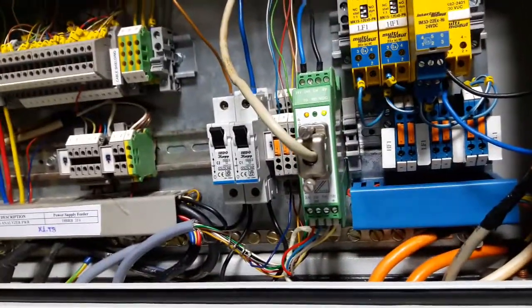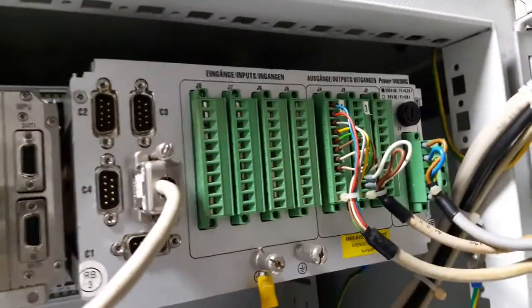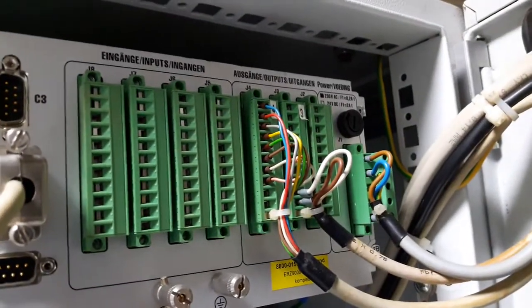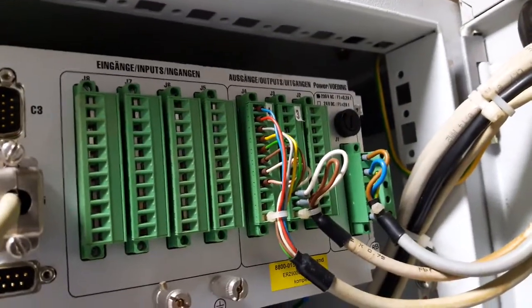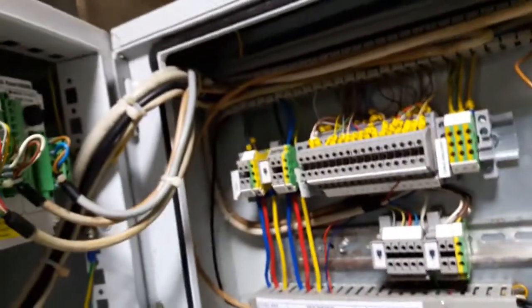You can see at the back of this display, this is the RS485, make Phoenix Contact. The top two are the 24 volts and the bottom are the signals coming from the sensor. And this is the back of the gas chromatograph. This is RS485, and those are analog outputs which will be given to the DCS if required. This runs on 230 volts AC.